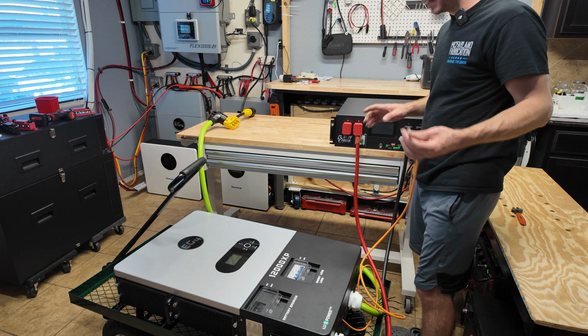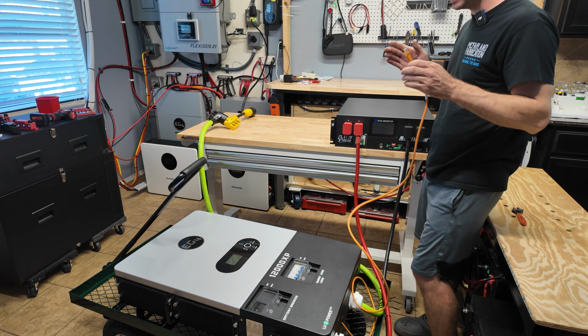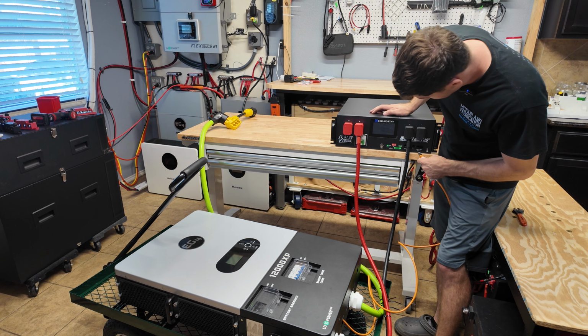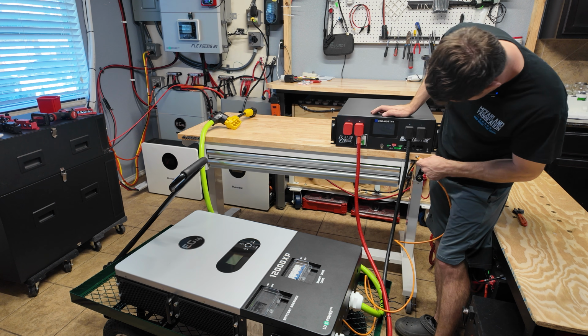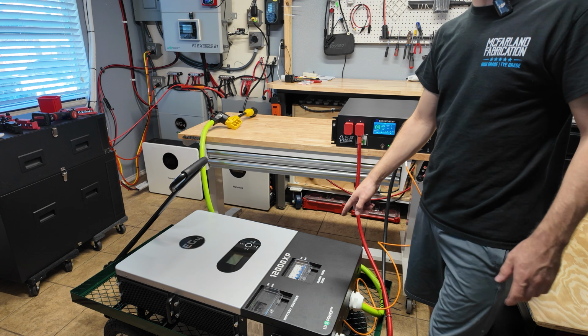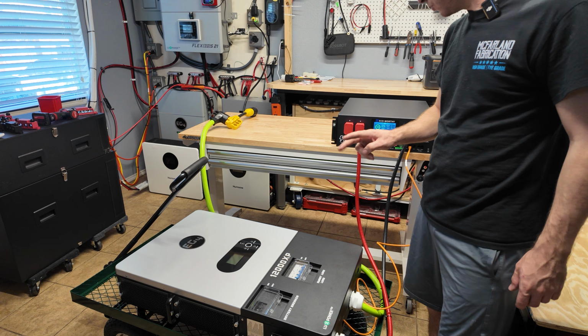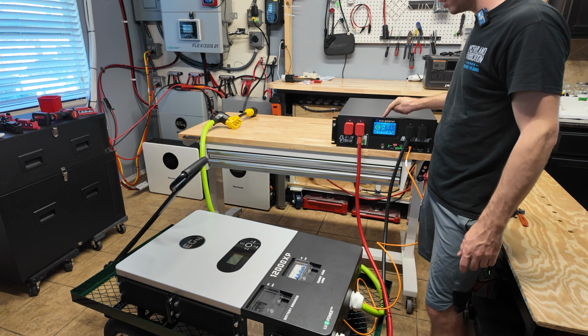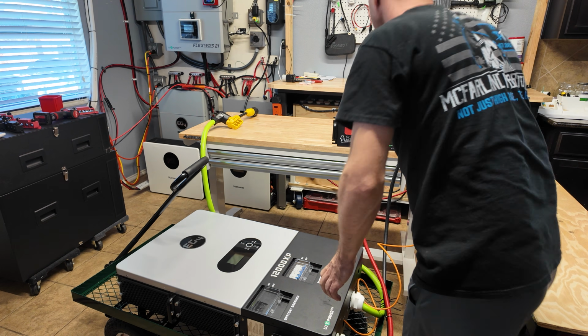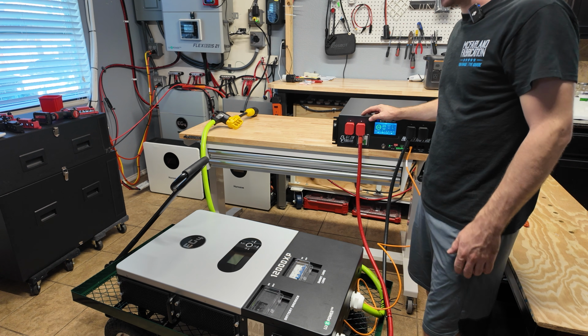Before I power everything up, I'm gonna connect the communication cable from the inverter to the battery so we can see if the comms work. We're gonna do CAN. I already have the inverter set to lithium mode 2, so all we have to do is set this to pylon and it should work perfectly. And that's it - it's already set to pylon out of the box, so we're good to go.